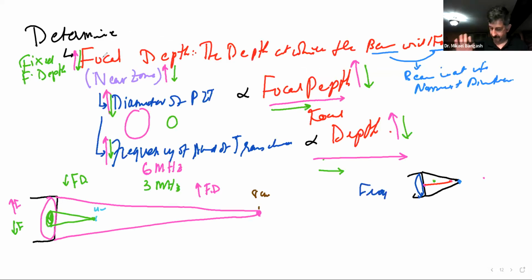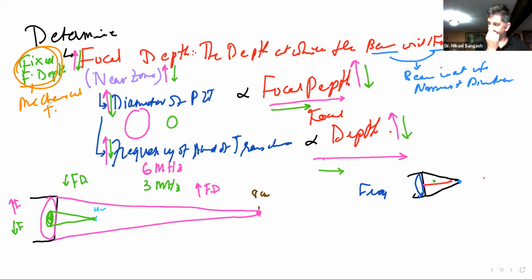If you got that, you should be good. But please keep in mind, this is for fixed focal depth transducers, or as we will later on call them, mechanical transducers. Is that clear? Yes. Good.